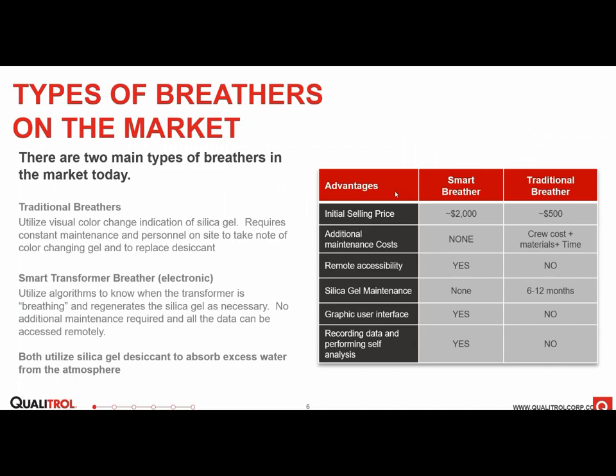So the current options for transformer breathers on the market, there are two big categories. We consider them either a smart breather or a traditional breather. A traditional breather utilizes a color changing silica gel, which alerts you as the utility when you need to change that silica gel, when it can no longer absorb any moisture. And if it is fully saturated, then moisture is just allowed to be inhaled into your transformer. So those operate on the basis that if the color indicates it needs to be changed, you need to send a crew out to the field, and that silica needs to be replaced.